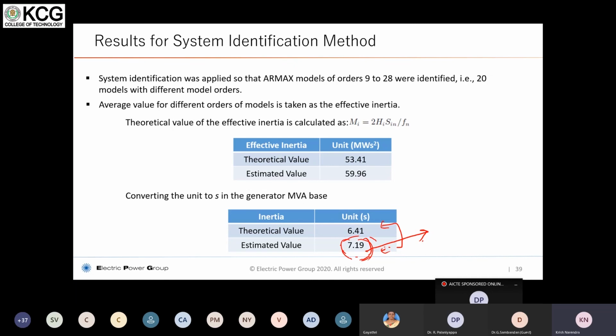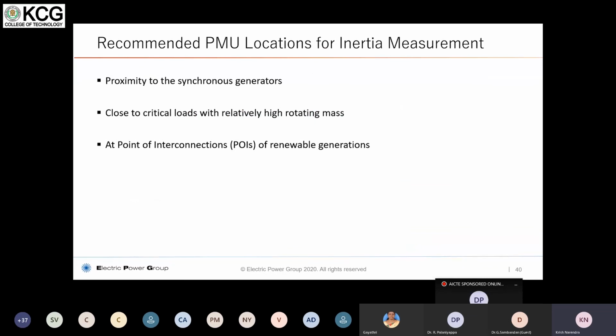But this particular methodology has been implemented successfully in Iceland, a country with fewer generators, using PMU data. The same methodology was implemented there, and they obtained excellent results using system identification. The recommended PMU locations for getting accurate inertia measurement are in proximity to synchronous generators. It need not be at the generating station, but as close to the generation as possible is good. Also critical loads with a very high moment of inertia and rotational mass support, and the points of interconnection of renewables. These are important locations where inertia measurement has to be done using PMU measurements.